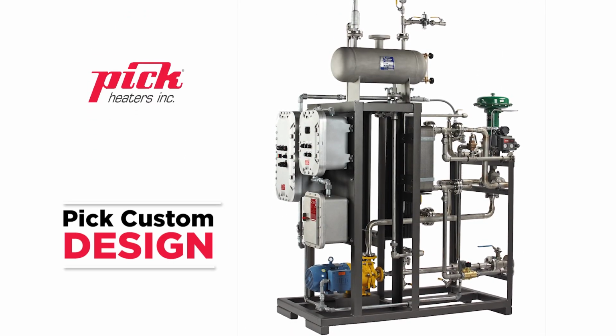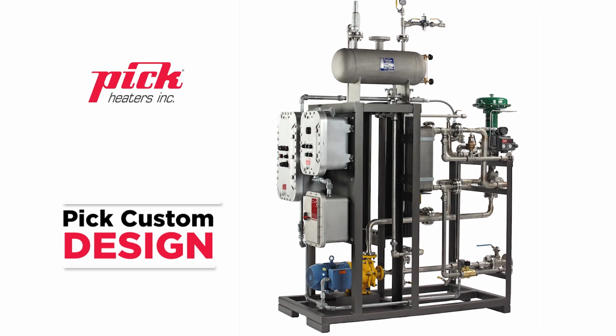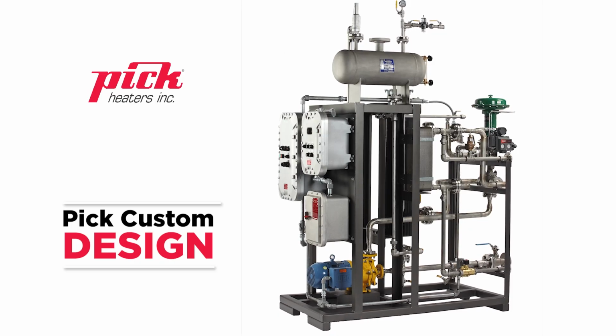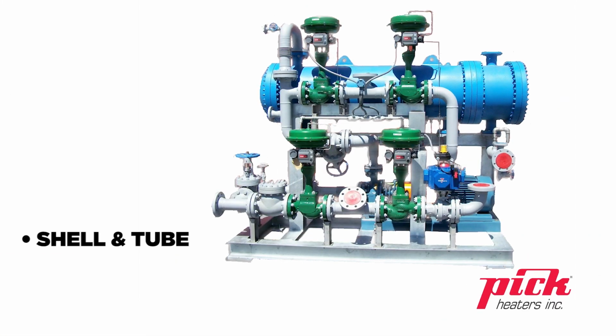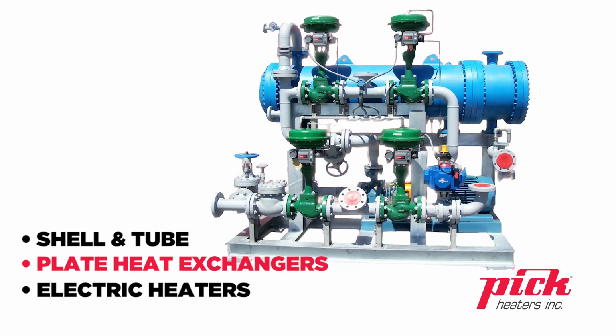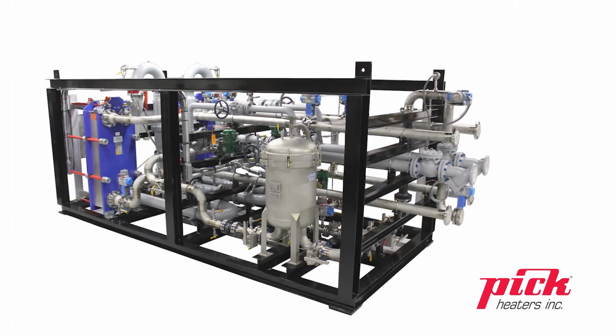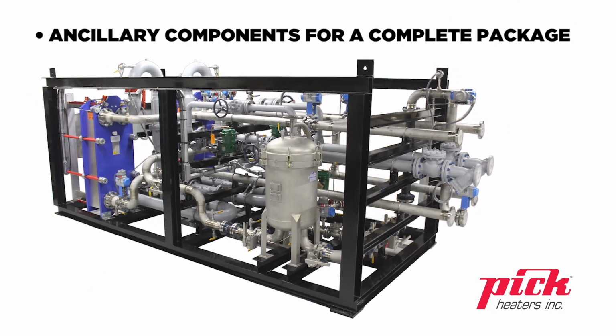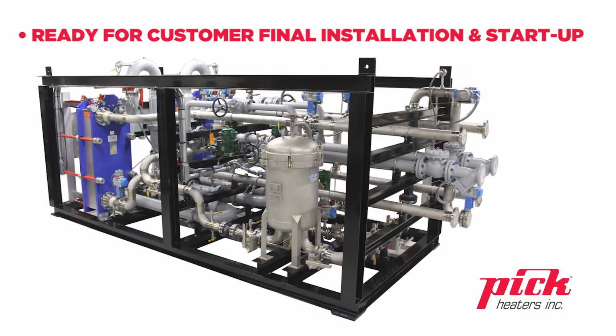Secondly, when using steam, multiple steam connections are required to lower the velocities to an acceptable range that these plate exchangers can handle. This can make system piping complex and very costly. And when needed, additional plates can also be required to lower those velocities.